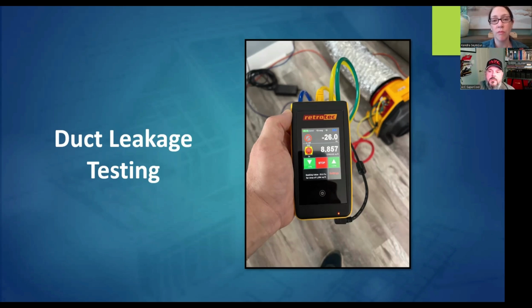If you have a system replaced, before we commission this system and start this blower, actually moving air through the system, let's do a duct test and see where we are, and find any deficiencies before we start pulling air that is unconditioned and unfiltered.